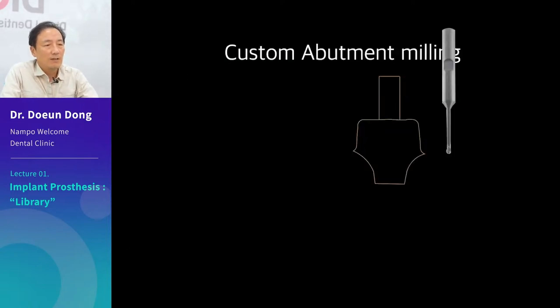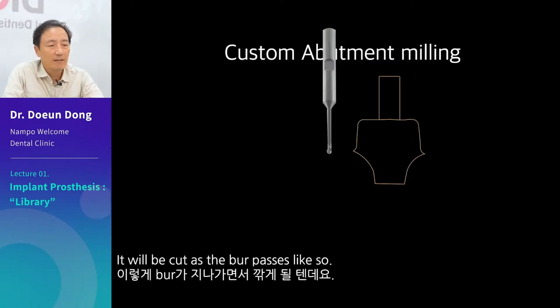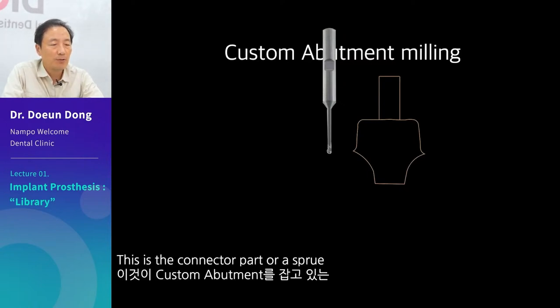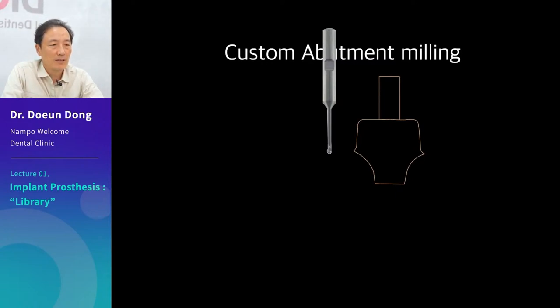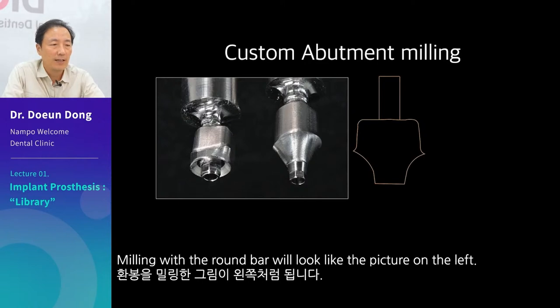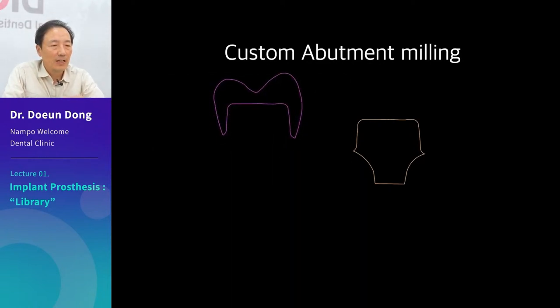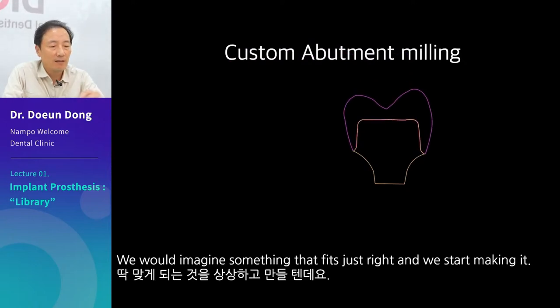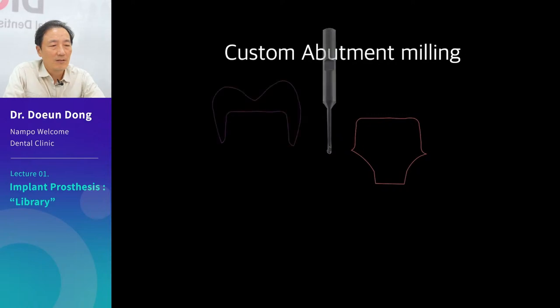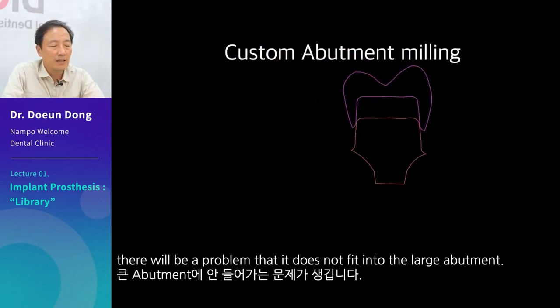There is a problem, however. This is a picture taken during custom abutment milling — it will be cut as the burr passes. You will see something protruding on top — this is the connector part or sprue holding the custom abutment, and it will always remain. Milling with the round bar will look like the picture on the left. The problem is how good the burr is in the milling machine. If the burr is worn out, it will cut excessively. Then, if a zirconia crown is made and fitted later, there will be a problem that it does not fit into the large abutment.